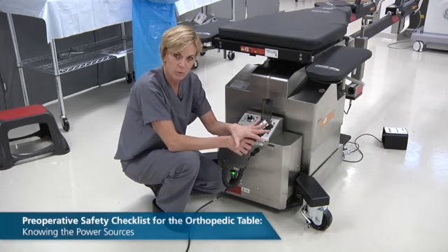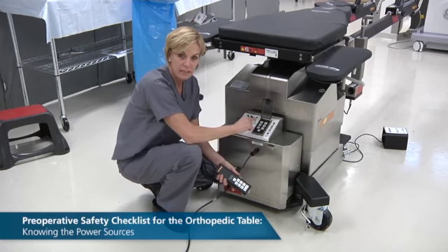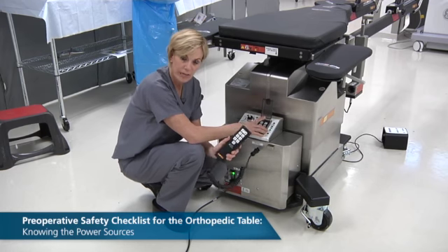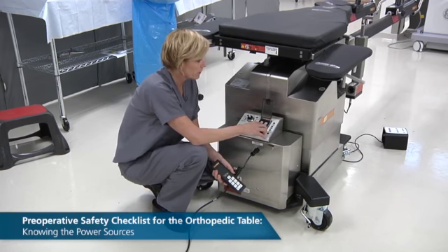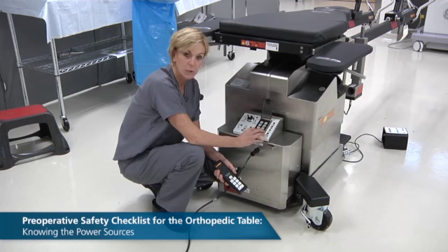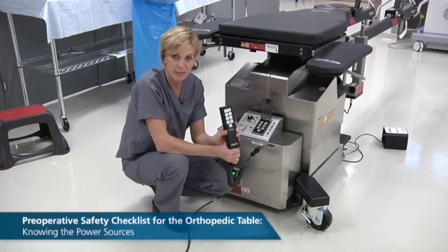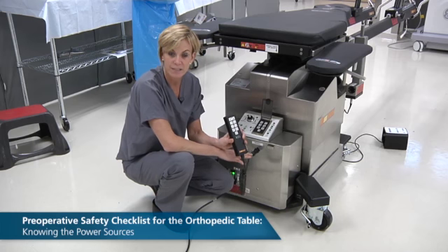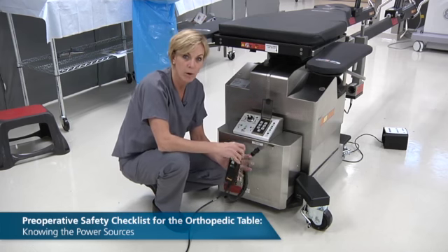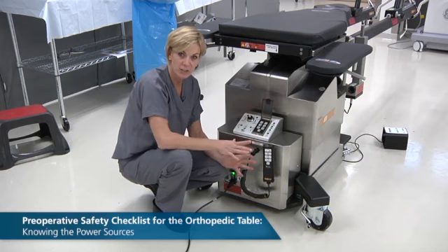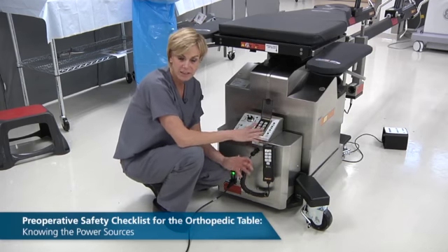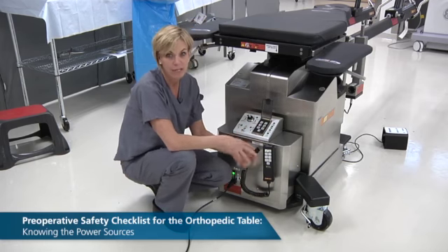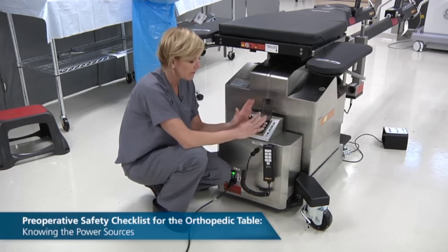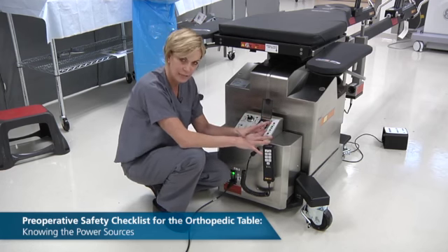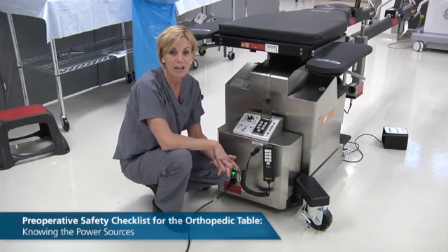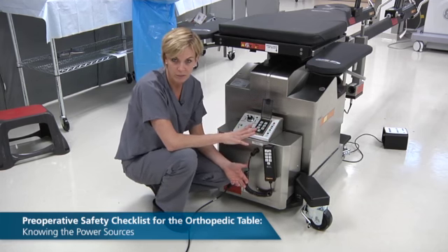If the hand control is not working, the first thing to do is see if the keypad works. So for example, if your hand control is not working, but your keypad is turning the table as you wish, it simply means that your hand control is not working or it's not attached to the table correctly, and that's an overcomable problem for sure. You can simply finish a case with the keypad as long as you have a willing CRNA or anesthesiologist. If, however, the keypad's not working and the hand control's not working, it indicates that you're not getting sufficient power to the table for some reason.